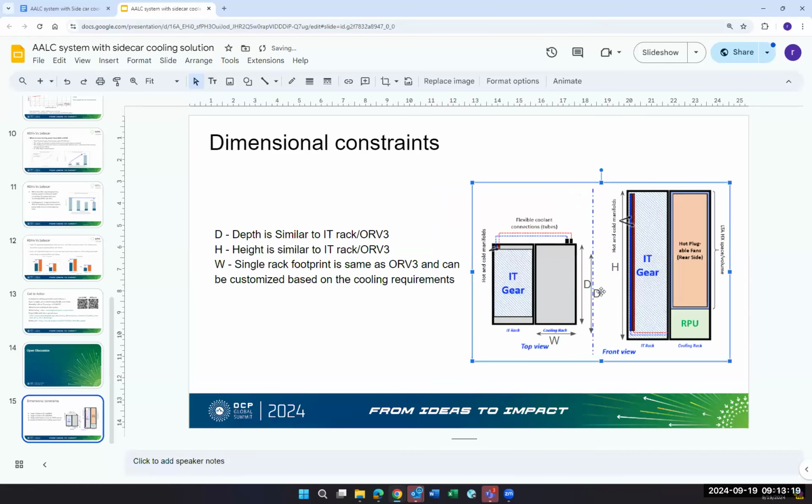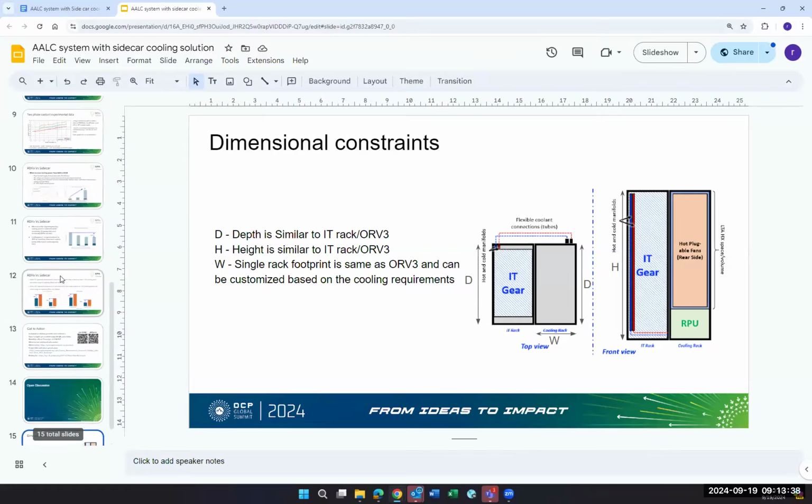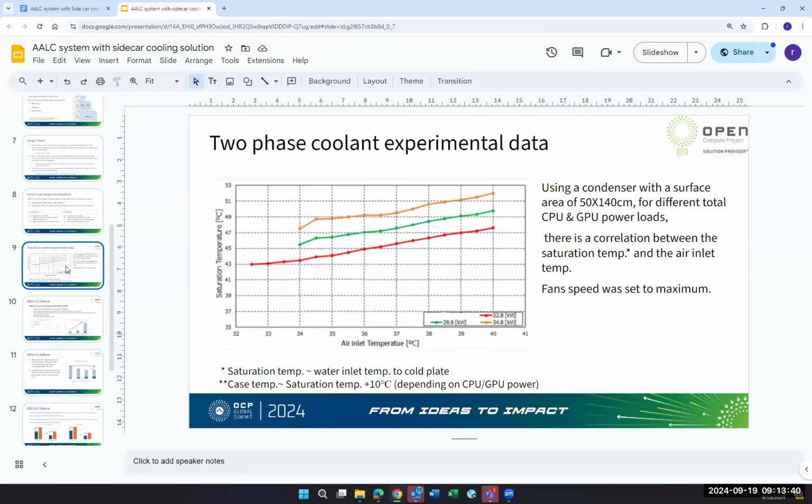Oh, yeah, that's true. You can say that it's for different sizes. The width calculation or the airflow calculation were done based on the capacity restrictions, and also what the restrictions are on the data center side and the airflow velocity restrictions on the heat exchanger side, right?